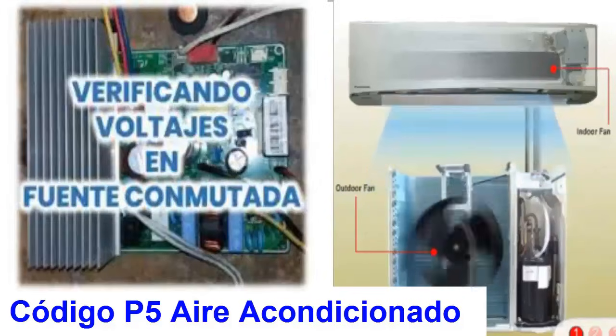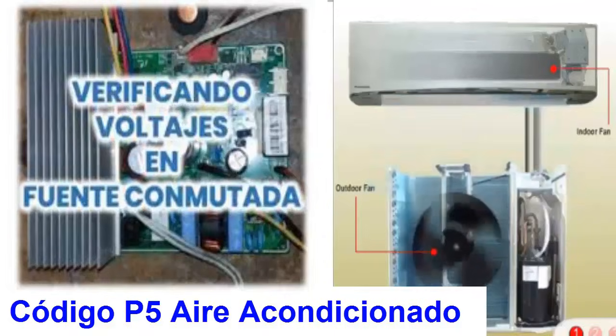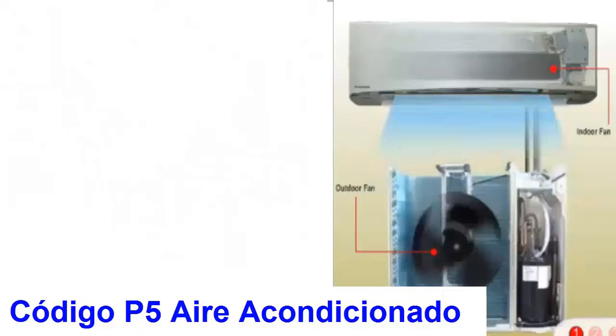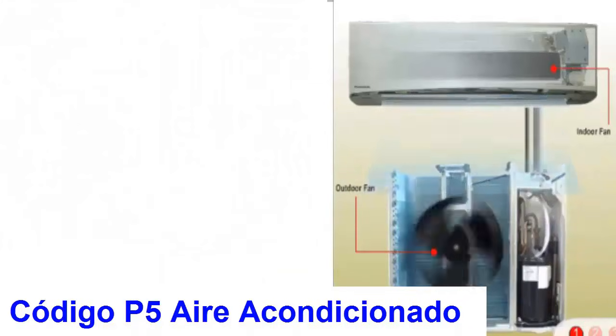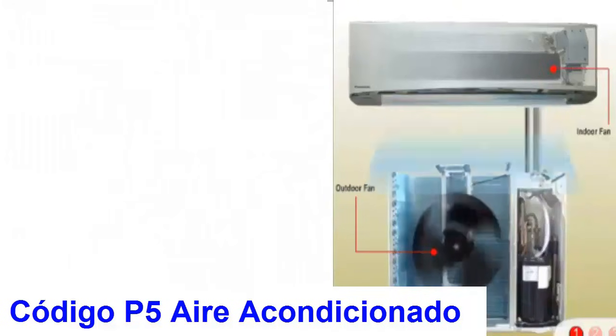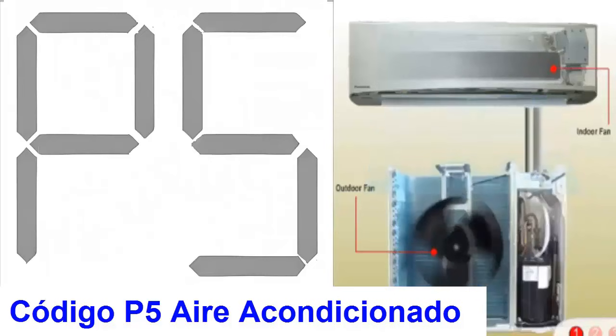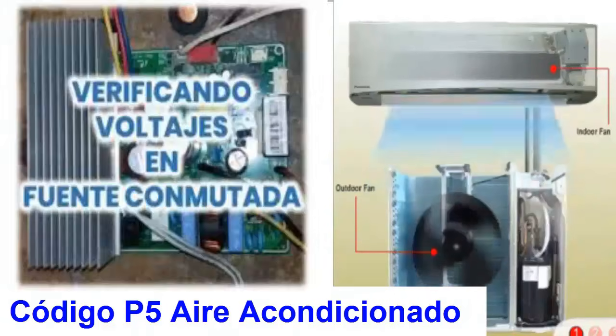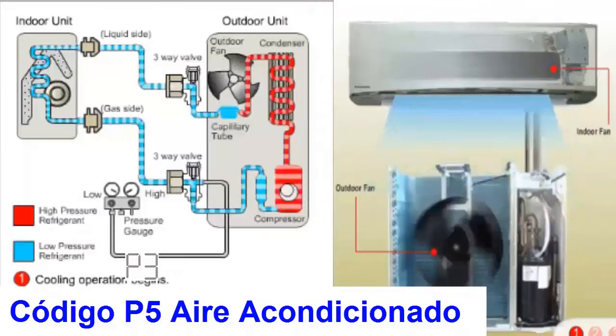7. For the manufacturer Midea, the P5 code is associated with inverter module protection. A series of checks should be performed, including electrical supply, condenser heat exchange, presence of obstructions on the high pressure side, and excess refrigerant. Additionally, the inverter system on the electronic board should be checked, and compressor replacement should be considered if necessary.